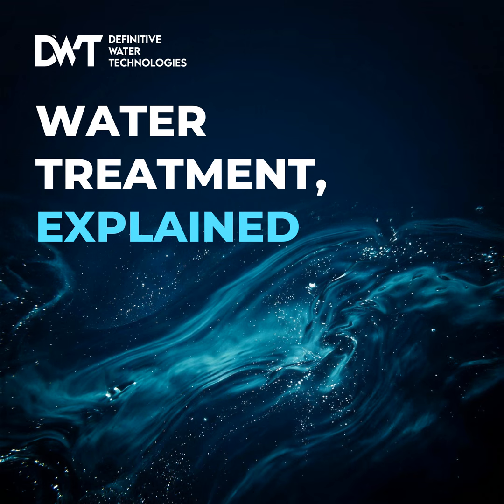Right. Test 1. Turn the pump OFF. Fill the clear calibration cylinder on the suction side, open the valves, and just watch it. And if the liquid level drops while the pump is off, you have a siphon fault. You fail immediately. Gravity is pulling it. You need to fix your back pressure valve.